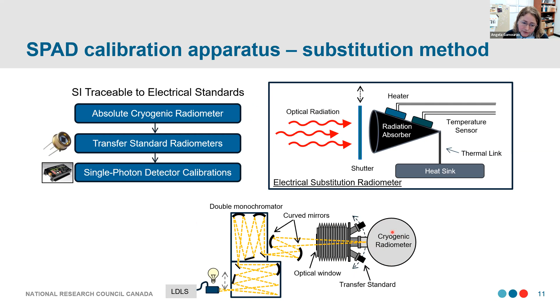It's operating at 4K to minimize noise. And we have a flexible bellows system, so we can have one optical path, and we can measure our light with our cryogenic radiometer or with our transfer standard detector.